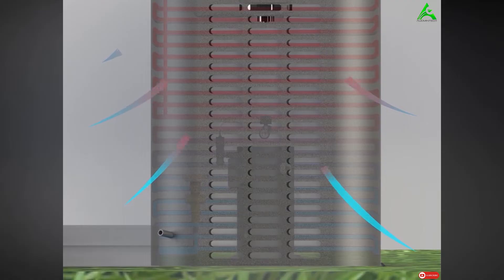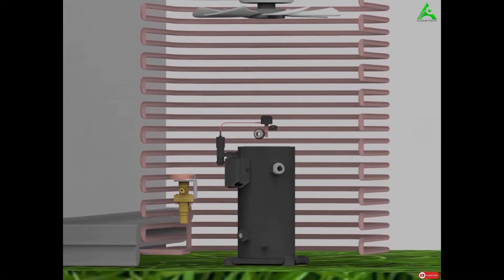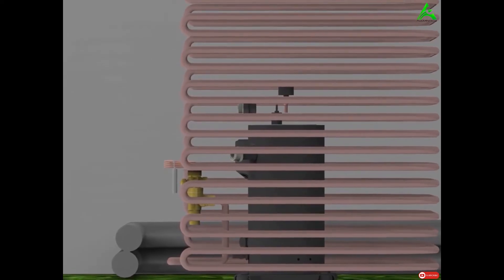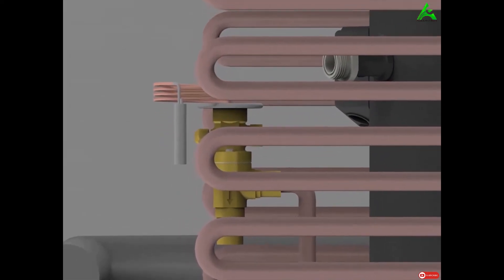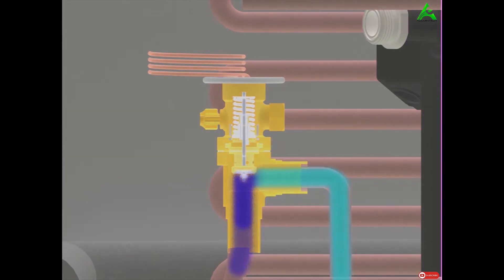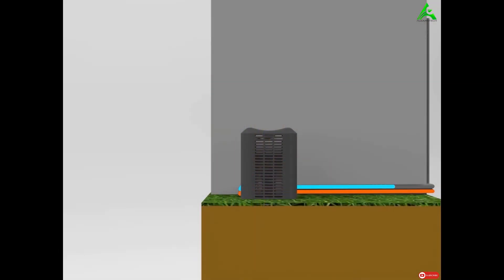The cooling process is aided by circulating air through the condenser coils. The medium temperature, high pressure liquid refrigerant then enters the thermal expansion valve. The valve decreases the pressure of the refrigerant, and finally it leaves as low temperature, low pressure liquid.